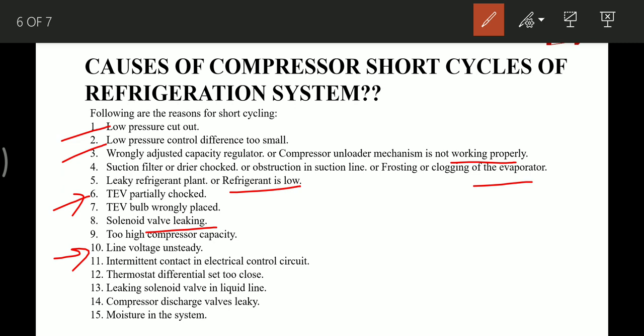Then intermittent contact in the electrical control circuit making and breaking the circuit for the compressor. Then thermostat differential set too close, meaning if the solenoid valve is operated by thermostats and its set values for opening and closing are very close to each other. Then leaky solenoid valve in the liquid line.